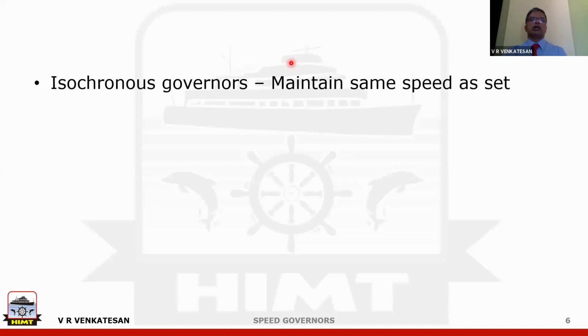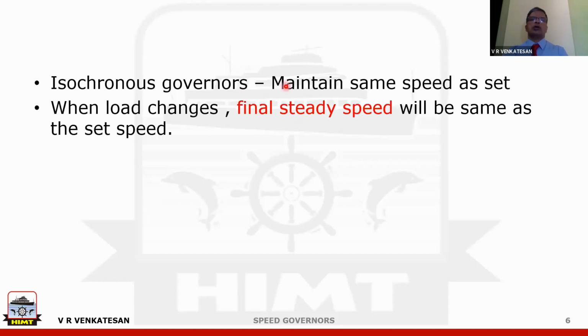So if I have an alternator running at 60 hertz controlled by an isochronous governor, it means if the kilowatt is increased or decreased, it will still maintain 60 hertz. Finally, it will maintain 60 hertz. That is the meaning of isochronous. So when load changes, the final steady speed will be the same as the earlier steady speed. The governor is an equipment which works very fast, so the final steady speed will be achieved in a matter of seconds, a very short period.